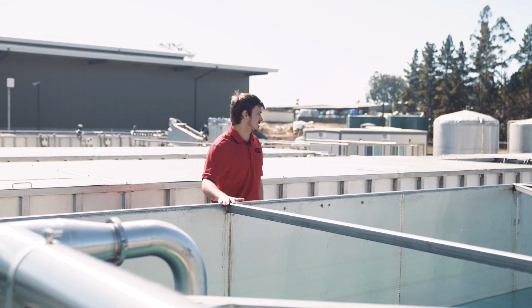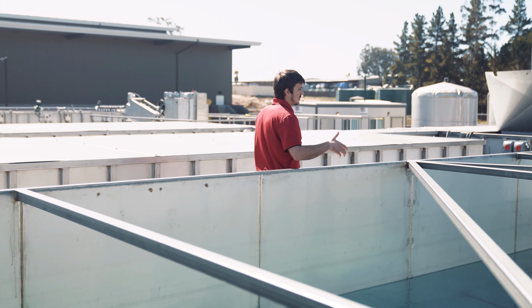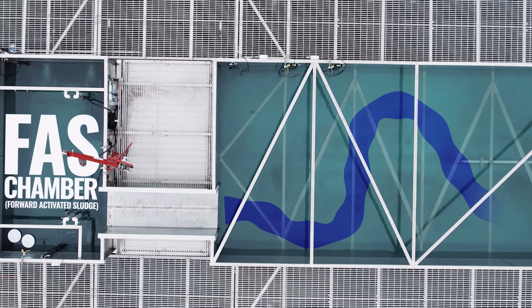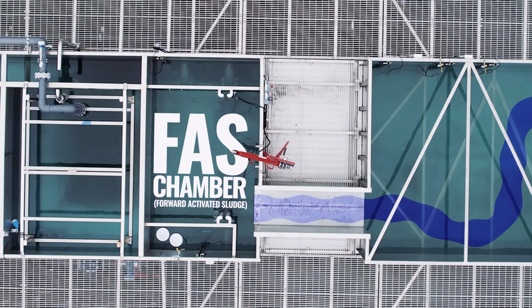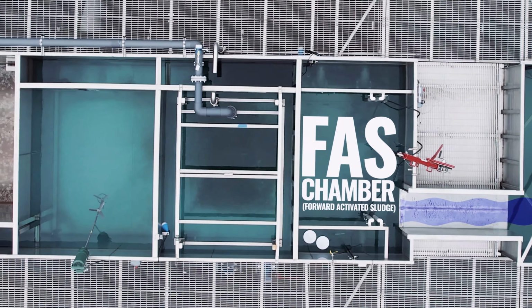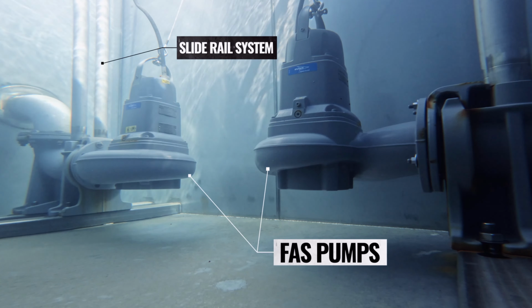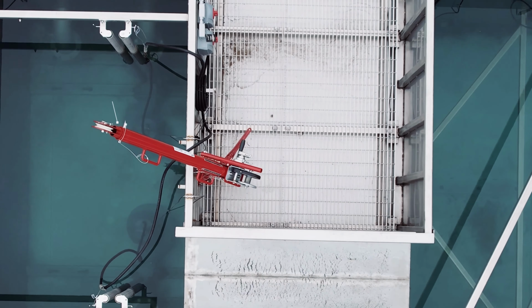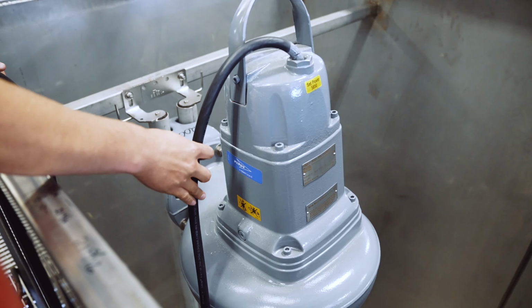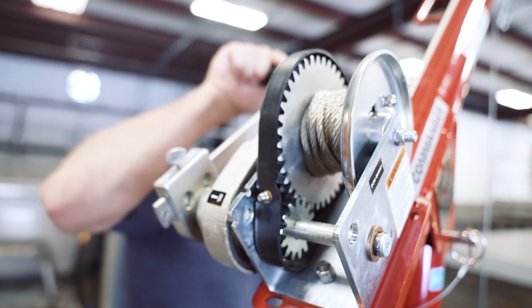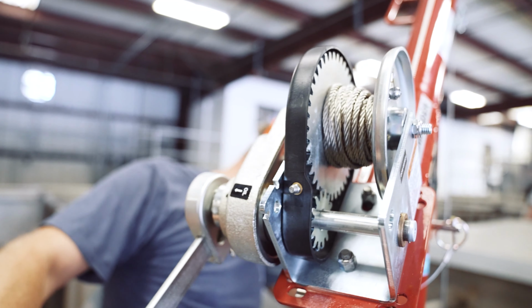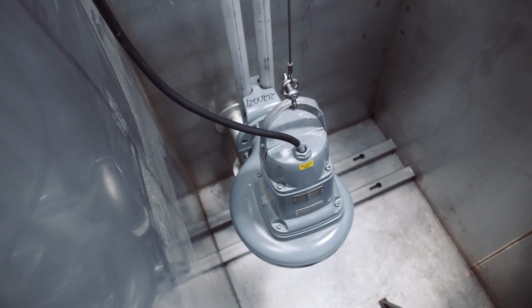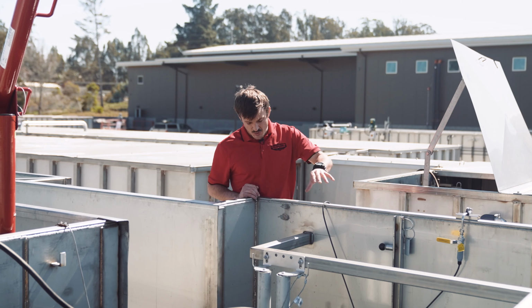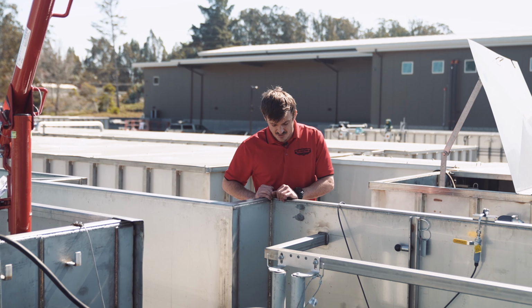On to the next process, we'll again overflow through the overflow channels into the forward activated sludge chamber or FAS chamber. The chamber has an individual dedicated FAS pump on a slide rail system, and with the slide rail system we'll provide a davit crane so that the operator can hoist the pump out of operation and inspect for routine maintenance and be able to easily drop it back down and not need a team of operators to require that removal process.